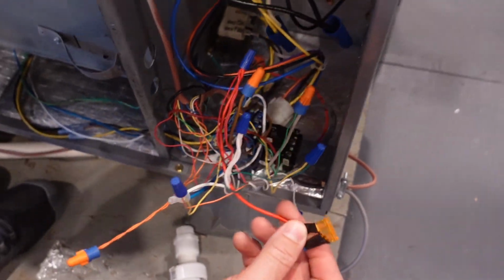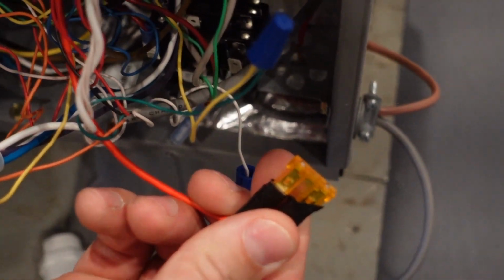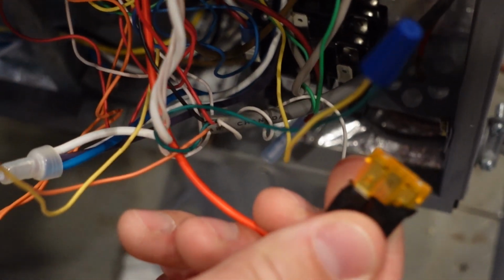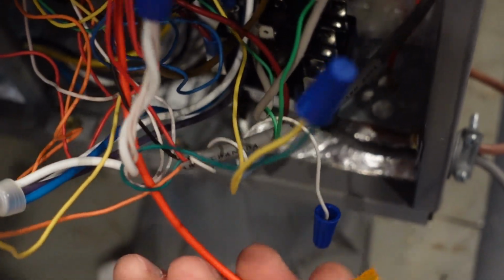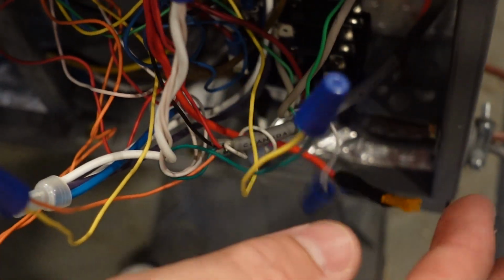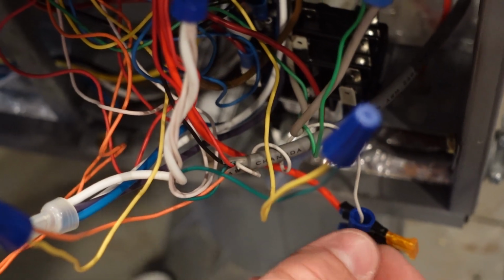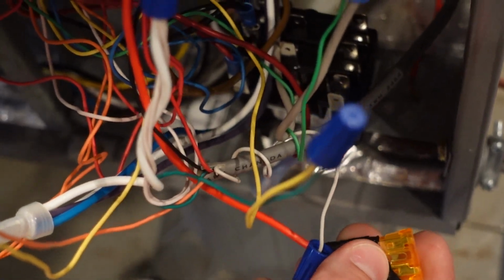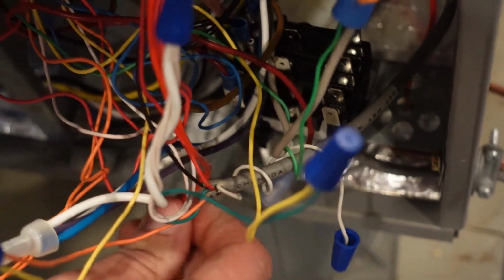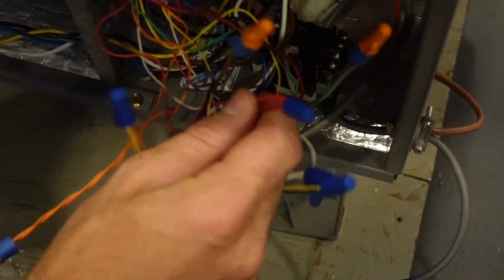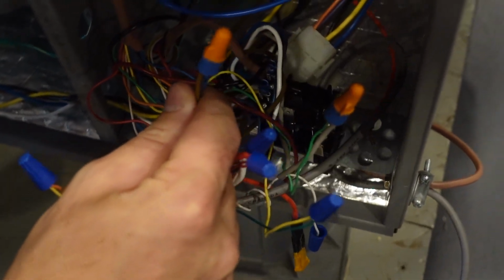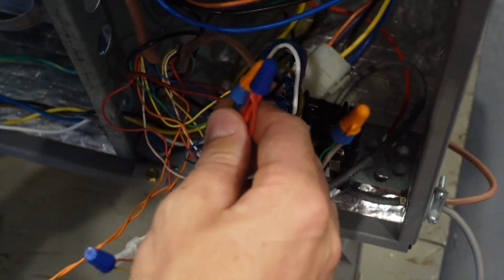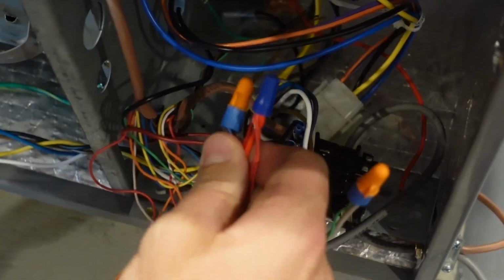So if you come out now, you'll see the next step in the low voltage circuit is the 5 amp fuse right here. And that 5 amp fuse is the sacrificial lamb for the transformer. So if there's an issue with the system in the low voltage aspect, it will blow this fuse before it allows the transformer to be blown. Now if we come out to the actual controls here, we've got the R terminal and the common terminal. If I measure across these two, I'm going to have 24 volts.